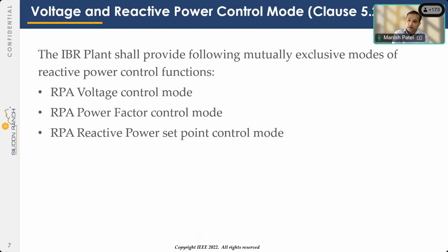All right, so then clause 5.2 states that the plant shall have capability to operate exclusively in the following control modes. One is RPA voltage control mode, another one is power factor control mode, the third one is constant reactive power control mode.